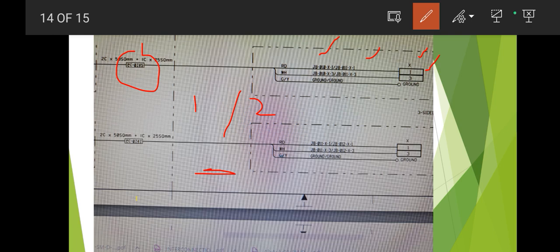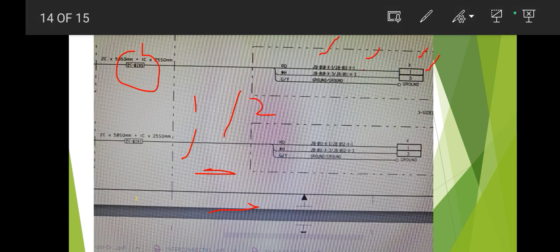Dash is different here. If you can see where the ferrule becomes half, it should be a slash. We have to use a slash. Slash means that one side of the ferrule is completed, and now you are going to start the other side. This is also a common mistake during construction. They make it a dash, so it's not correct, it should be a slash. So these are our wiring ferrules. I think everyone understands very well.